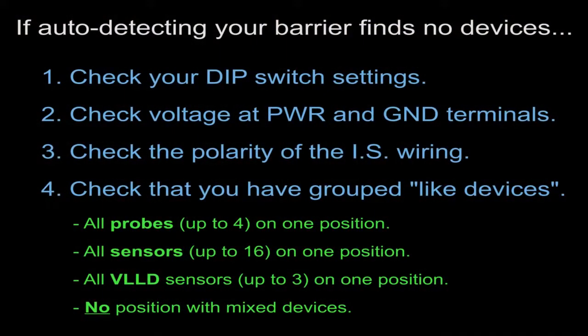Now you can't mix sensors and probes together. You have to wire all of your probes on one wire, and all of your sensors on one wire. And the limitation is that I can have 4 probe wires connected to one wire running back to the building, and I can have up to 16 sensors running back to the building on one cable.